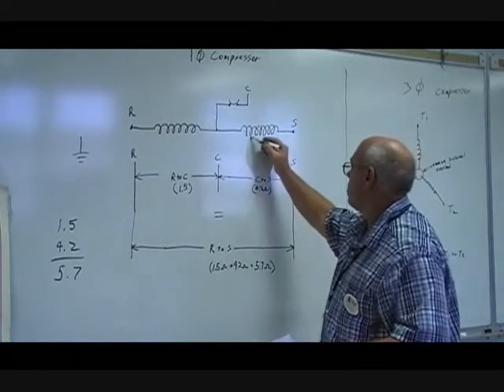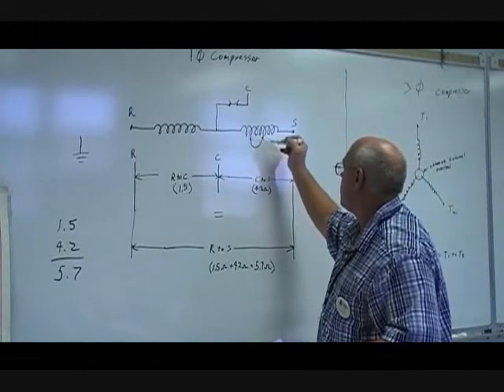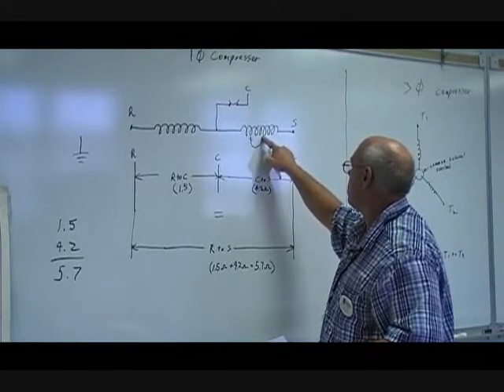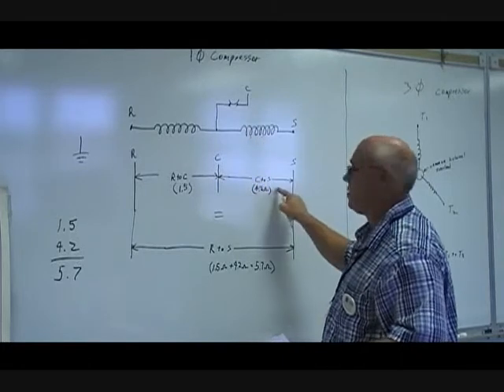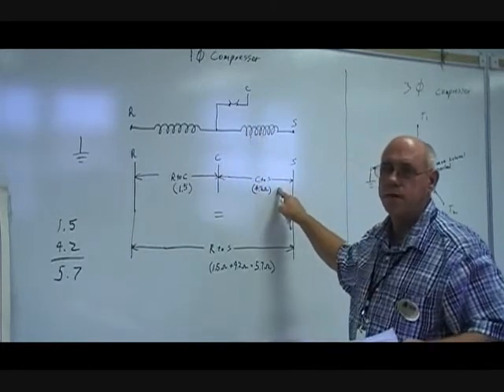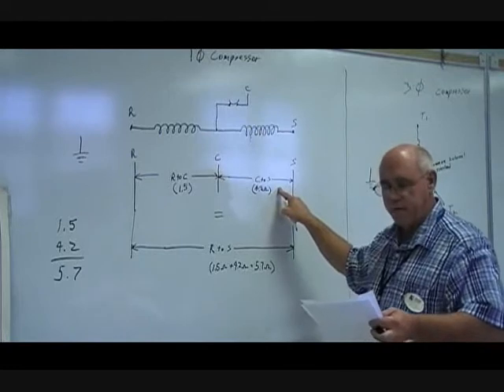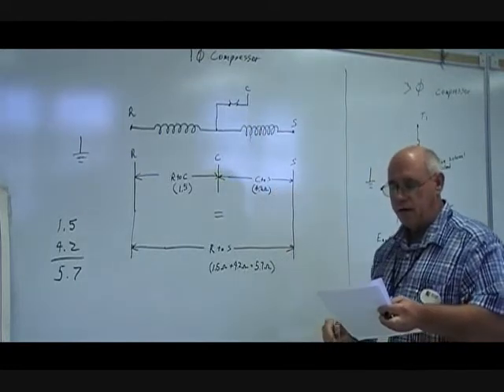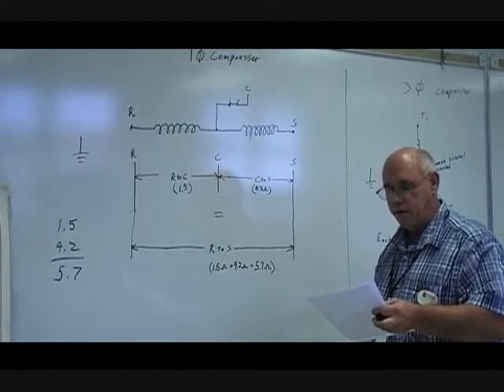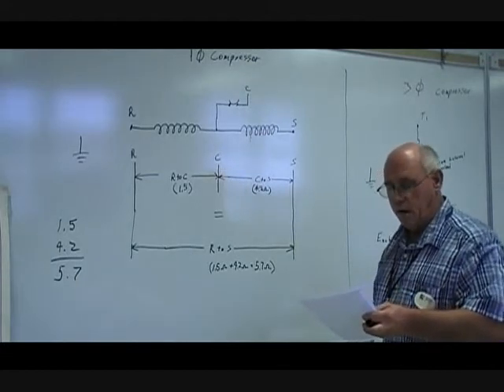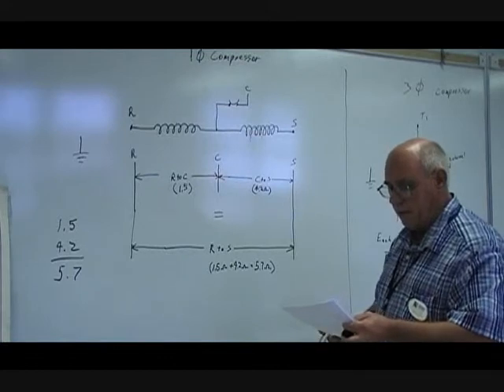Sometimes you may actually have a turn to turn short, where somewhere inside that motor, these two terminals, or these two windings, have come together. What's going to happen is it's going to read too low. About the only way to tell that is through the manufacturer's specifications. A lot of times that's hard to determine, but it will make the compressor run extremely hot and pull too many amps while running.